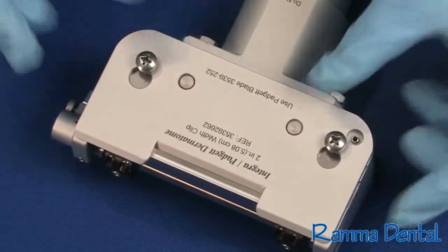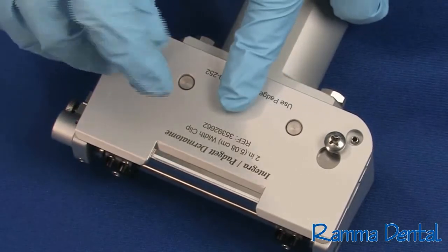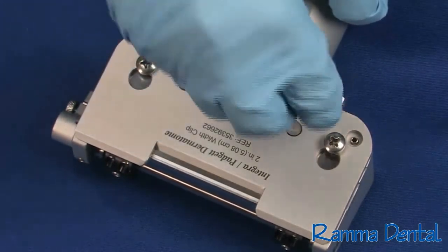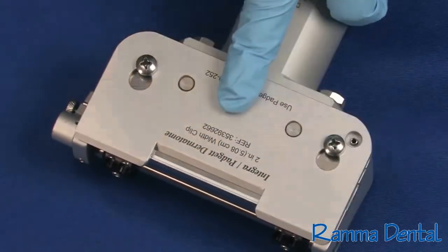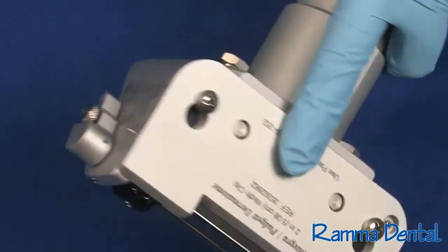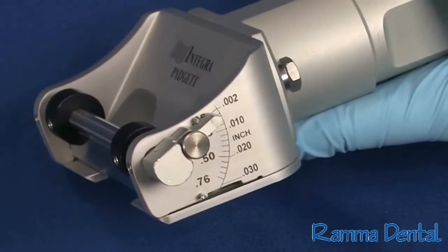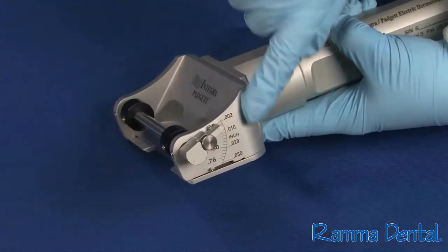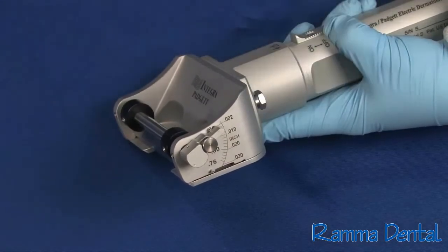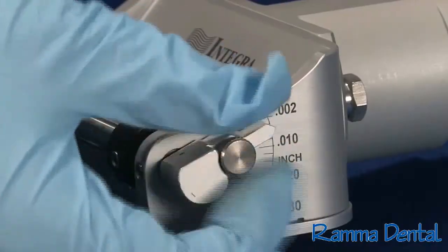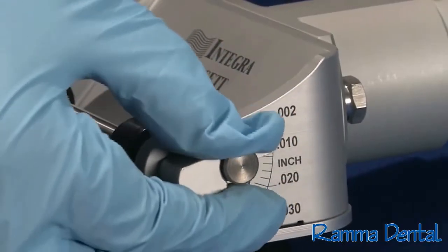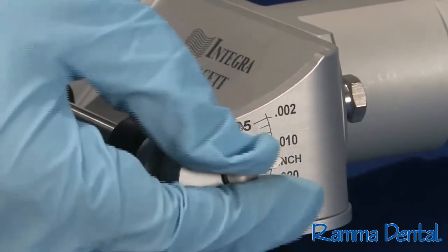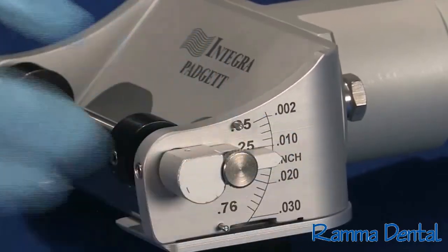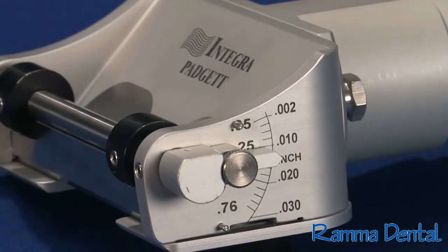The width clip is then placed on the top of the blade and screwed into place with the screwdriver. The clip should be snug but not extremely tight. The thickness of the graft is determined by the surgeon using the calibrated scale on the head of the electric dermatome. To adjust, first loosen the screw on the scale, then move the scale to the desired thickness and retighten the screw. Be sure to loosen the thumb screw prior to rotating the knob to a new thickness setting.